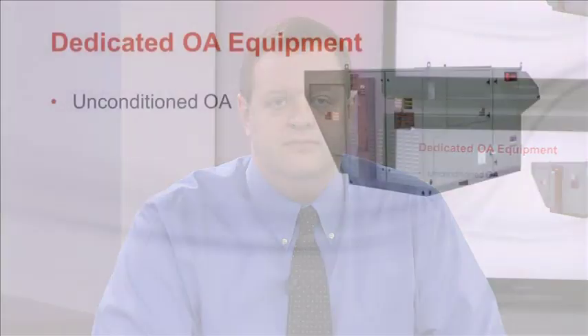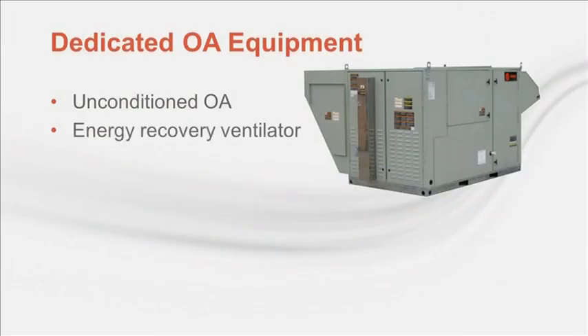So I talked about how the outdoor air gets to the zones, but what about where it comes from? I suppose in some cases the outdoor air might be unconditioned and ducted directly to the indoor units. It's simple, but this practice should probably be limited to just the dry, mild climates. In other applications, an energy recovery ventilator might be used. This reduces the ventilation load, but requires an exhaust air path and extra fan. And it does not dehumidify the outdoor air to a dew point that's drier than the space.